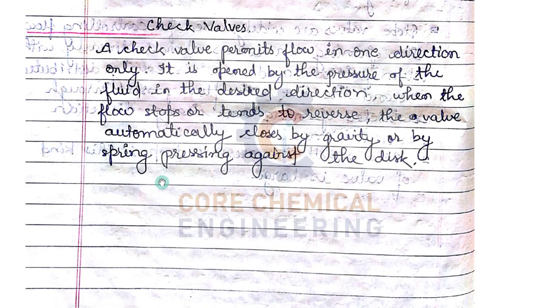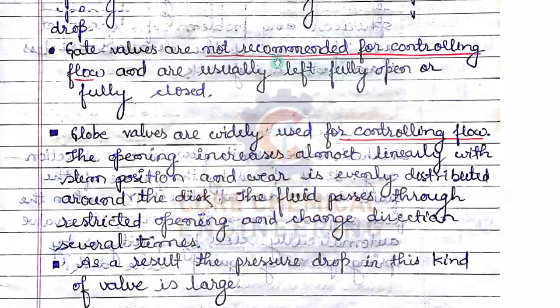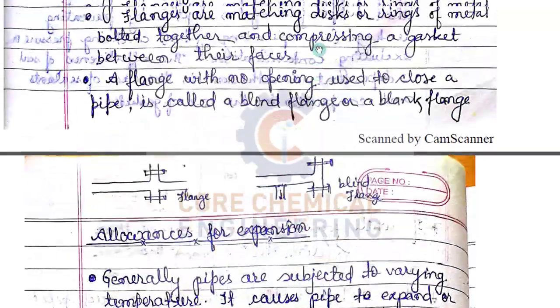A check valve — also called a non-return valve (NRV) in industry — permits flow in only one direction. It is opened by the pressure of the fluid in the desired direction; when flow stops or tends to reverse, the valve automatically closes by gravity or spring action pressing against the disk. Check valves play a very important role in safety, preventing downstream process fluid from flowing back into the system.